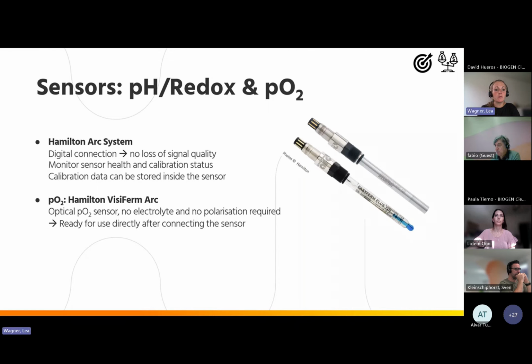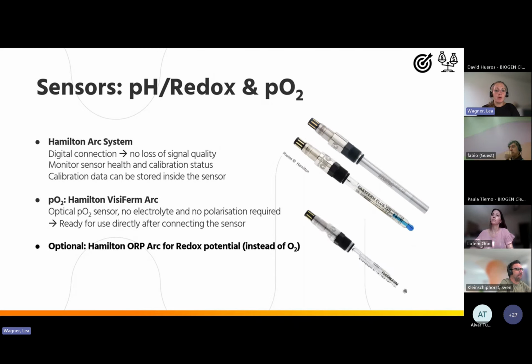And the Hamilton oxygen sensor, of course, is also digital, and it's also an optical pO2 sensor, which means that no electrolyte and also no polarization is required. And this saves time, because usually polarization takes around 6 hours. So this is valuable time the customer can save by using an optical pO2 sensor. And as an option, a redox sensor from Hamilton is also available instead of the oxygen sensor.